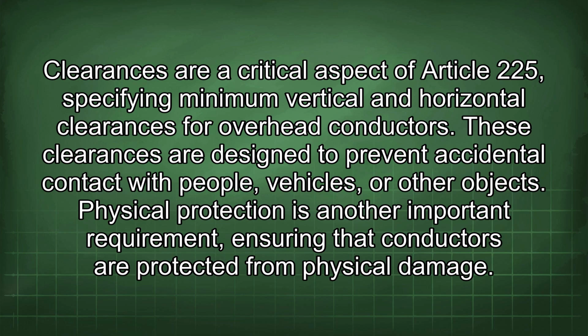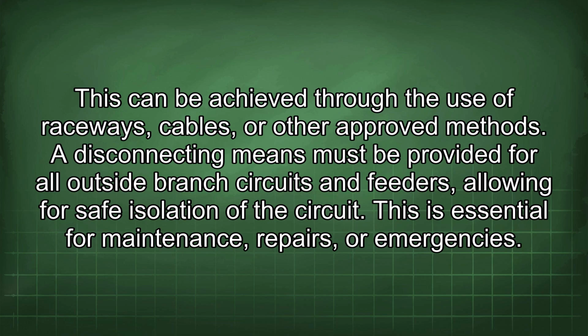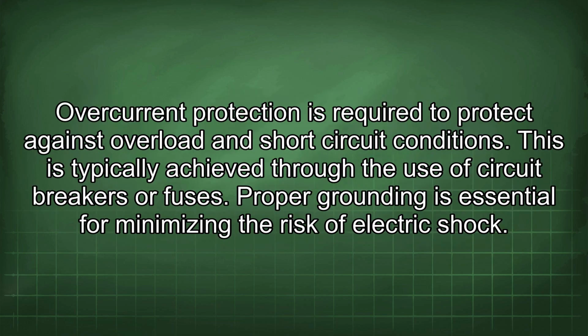Physical protection is another important requirement, ensuring that conductors are protected from physical damage. This can be achieved through the use of raceways, cables, or other approved methods. A disconnecting means must be provided for all outside branch circuits and feeders, allowing for safe isolation of the circuit. This is essential for maintenance, repairs, or emergencies. Overcurrent protection is required to protect against overload and short-circuit conditions. This is typically achieved through the use of circuit breakers or fuses.